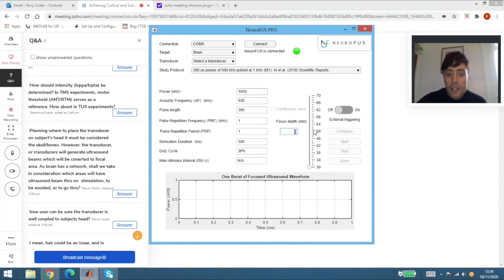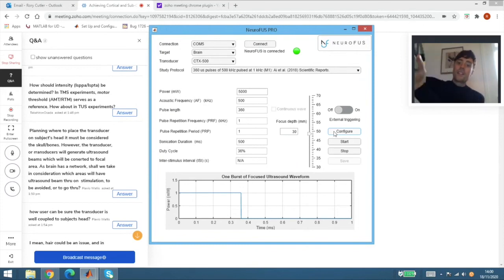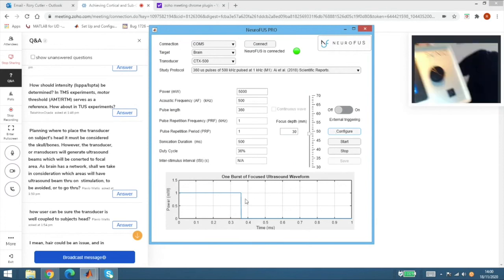Then all you need to do is select the focus depth from this nice little slider here, which you can do with that. And then you select your transducer, because that will make sure that the frequency you're choosing in the acoustic frequency window can be achieved by the transducer you have connected. Then click configure, and it will configure the NeuroFUS device, which I've conveniently got situated here.